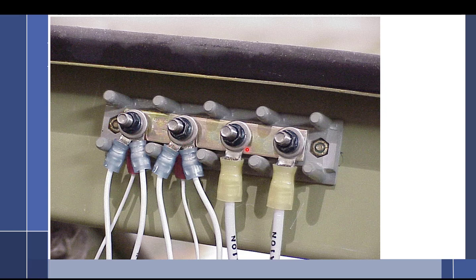But a couple of points about these. This is a terminal strip. There's some questions that talks about a terminal strip. That's called stacking. A couple of things about this - you might want to write this down. Number one, that this stud doesn't rotate. That the stud is secure behind this phenolic block. This is phenolic, by the way, it's like a plastic.